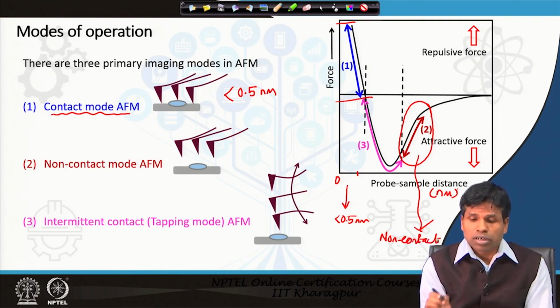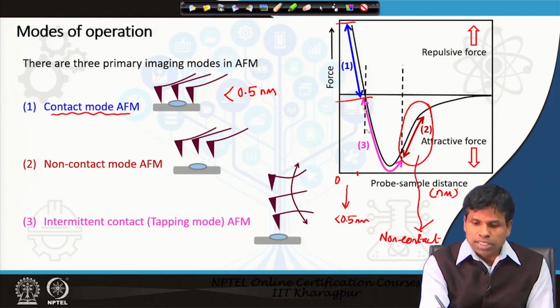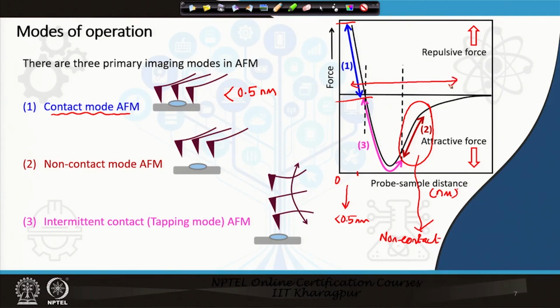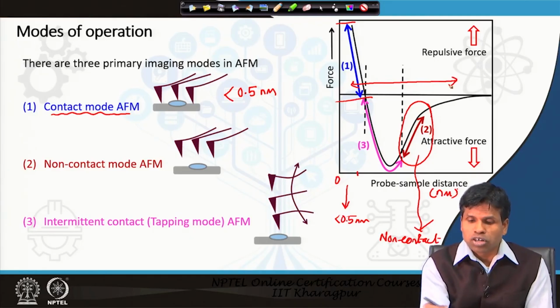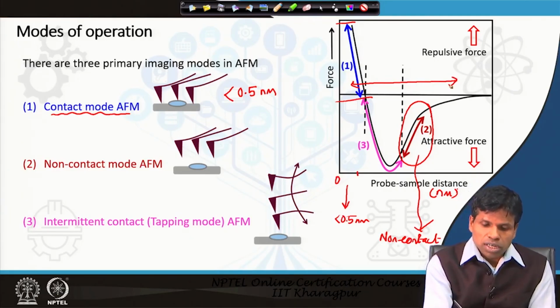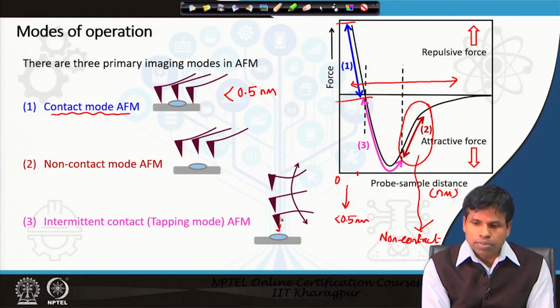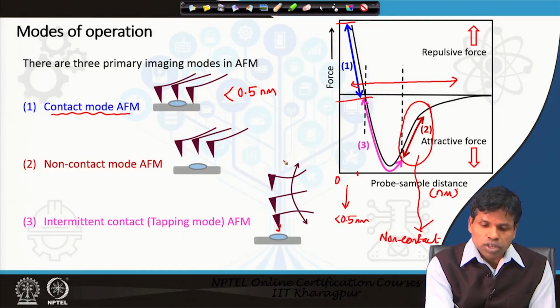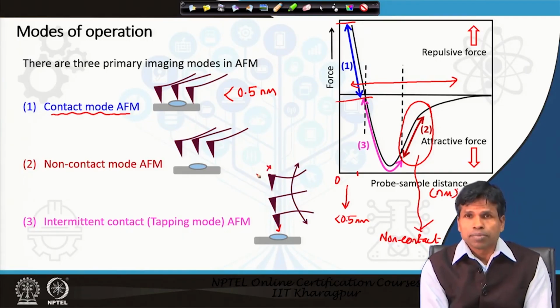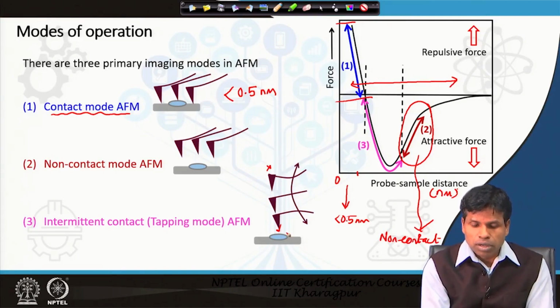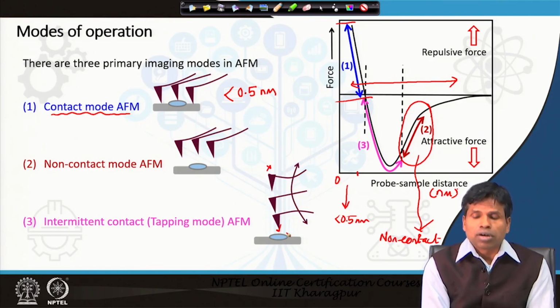Then between this contact and non-contact mode, in the middle portion, this is the region which is called the intermediate region, when the tip goes from attractive to repulsive region, or almost where there is no force of interaction to the repulsive region, then we say it is a tapping mode. In the tapping mode, as you see here, the tip is going close to the sample, that means it is going to the repulsive force region of the sample, and then it is going back upward where there is no force between the tip and sample, and when this tip goes backward and forward above the sample, then we say it is intermittent contact or tapping mode of measurement.